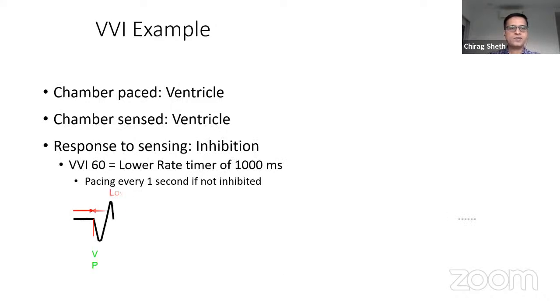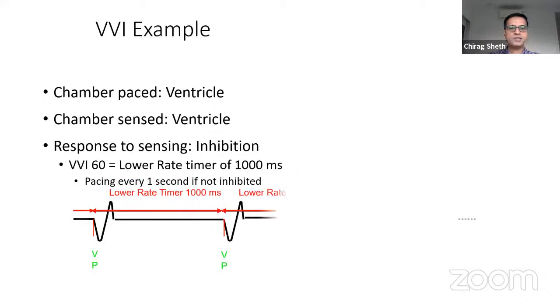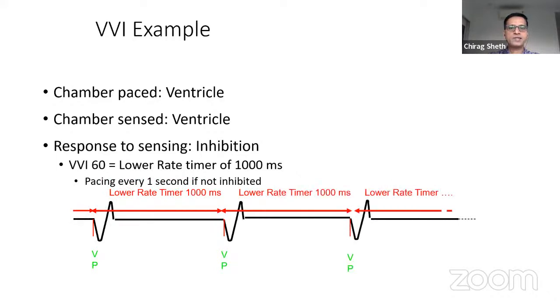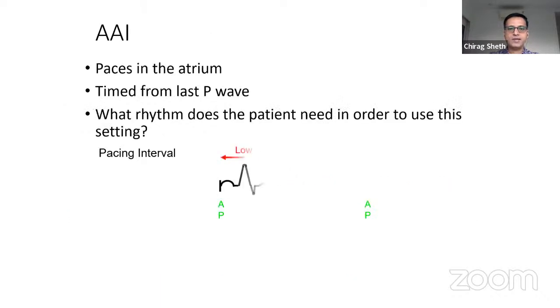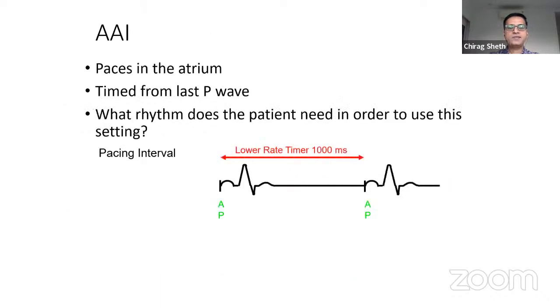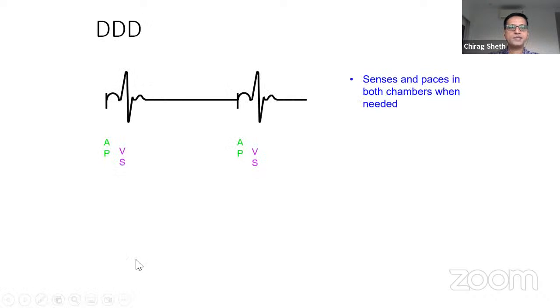So this is how, typically, if a patient has a lower rate programmed at 60, it will keep on giving impulses at the rate of 60. If it is AAI, it will give impulse into the atrium, and one can see a spike followed by a P wave and then the QRS. If it is dual chamber, here the event is happening because of pacing in the atrium, but the ventricular event is being sensed, so it does not pace into the ventricle.